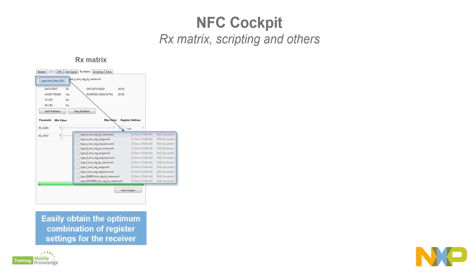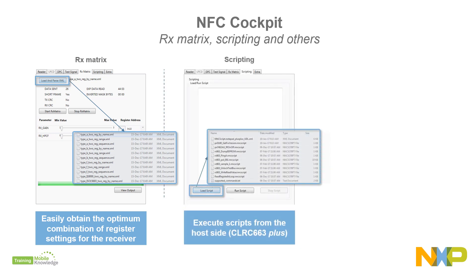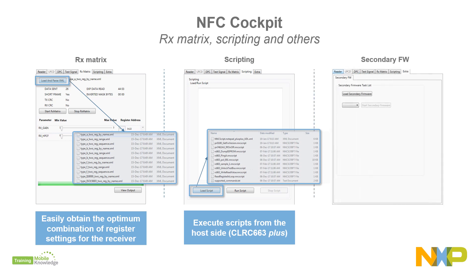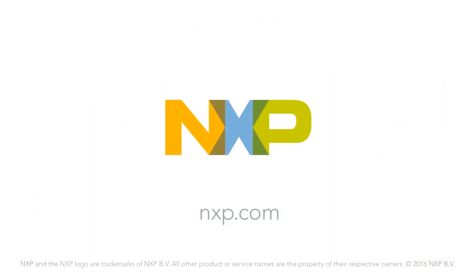Last but not least, the RX-Matrix test tool allows you to find the optimum receiver settings. In addition, an arbitrary waveform generator can be used to retrieve PCD sensitivity plots. You can import pre-programmed scripts to be executed from the host side, and you can also load a secondary firmware application from several files offered in the installer package, such as the EMVCO loopback application or the card emulation function. More information at www.nxp.com.